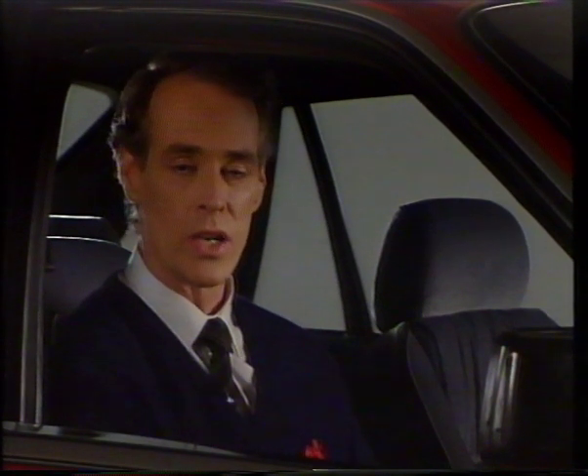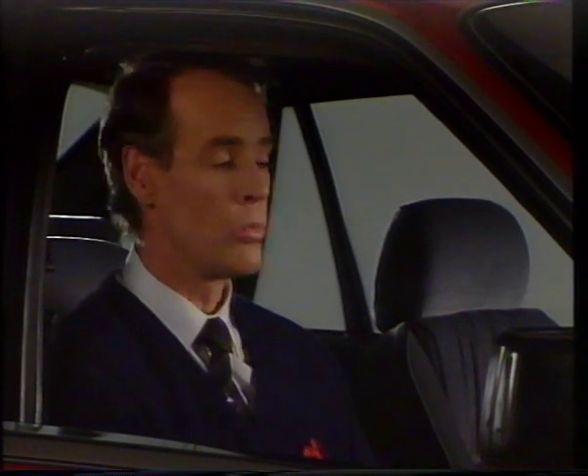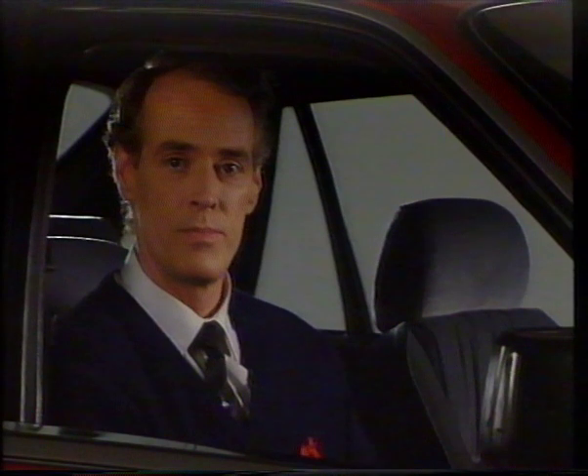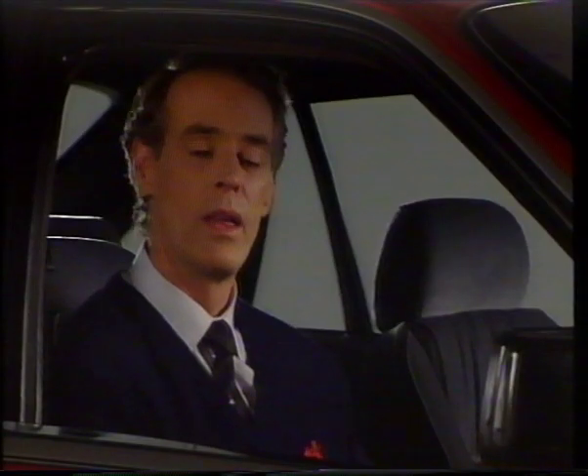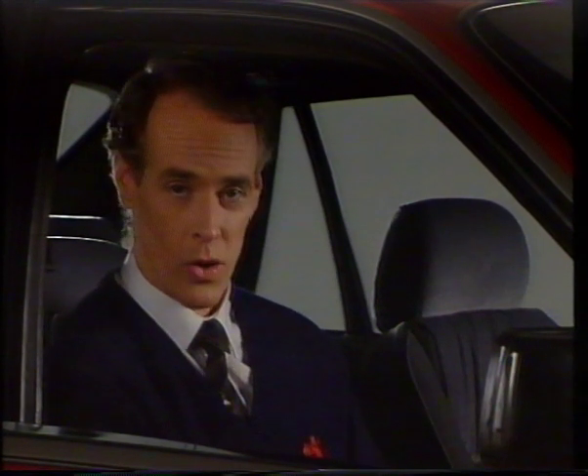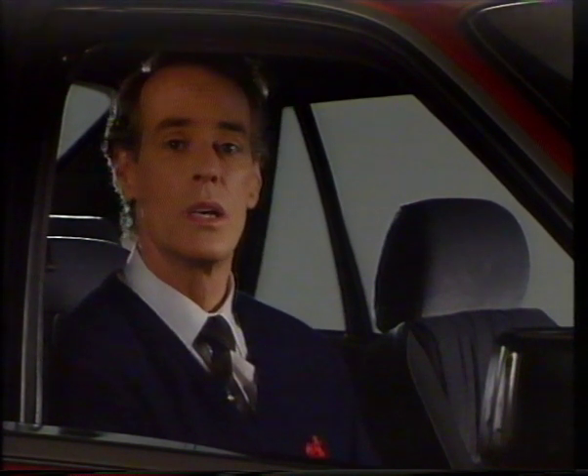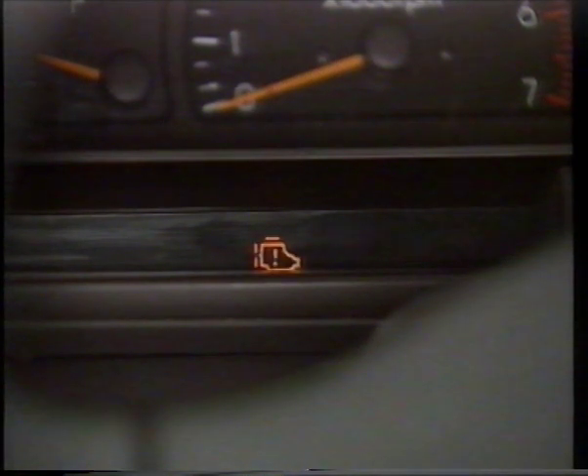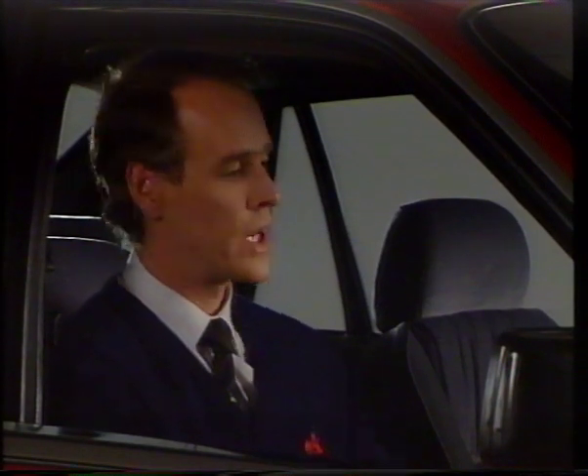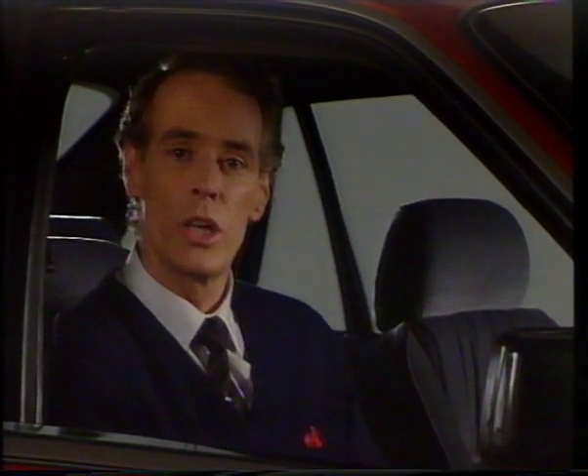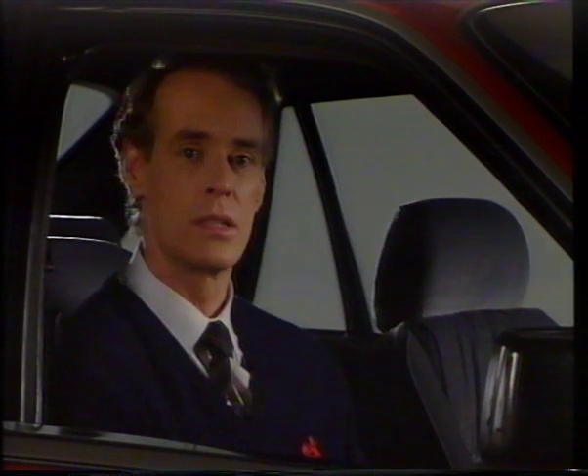If there are no malfunction codes, then the ECM will flash a code 12. That's one flash, pause, then two flashes. If, say, a code 34 was present, the sequence would be 3 flashes for 30, pause, then 4 flashes, giving us a code 34. Each code will flash 3 times, working from the lowest number to the highest.